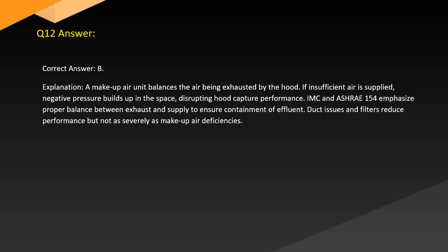Answer. Correct answer: B. Explanation. A makeup air unit balances the air being exhausted by the hood. If insufficient air is supplied, negative pressure builds up in the space, disrupting hood capture performance. IMC and ASHRAE 154 emphasize proper balance between exhaust and supply to ensure containment of effluent. Duct issues and filters reduce performance, but not as severely as makeup air deficiencies.